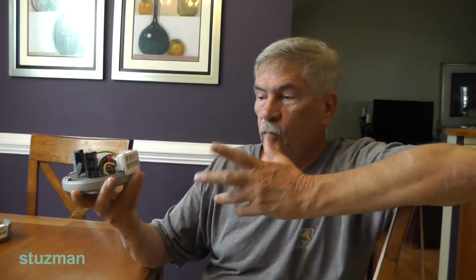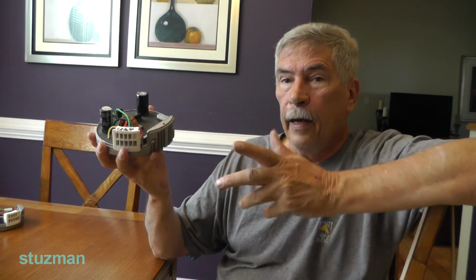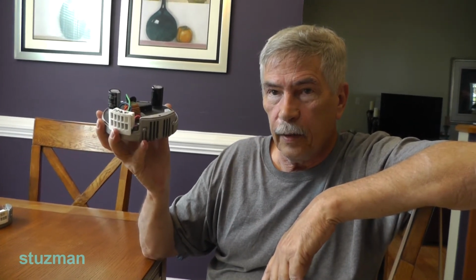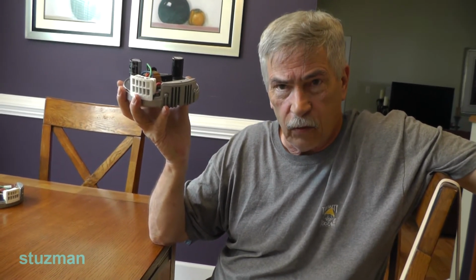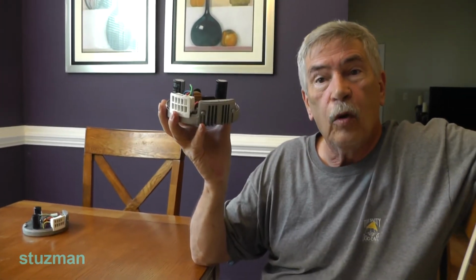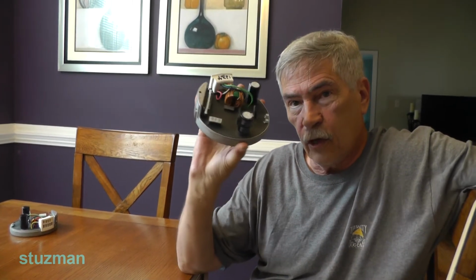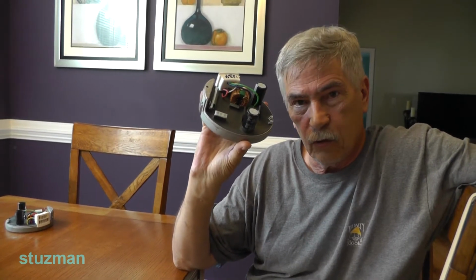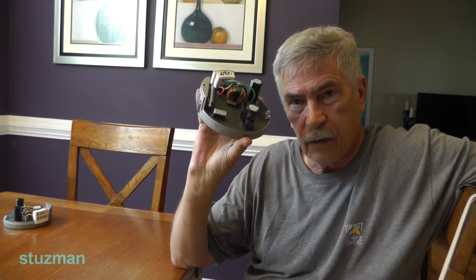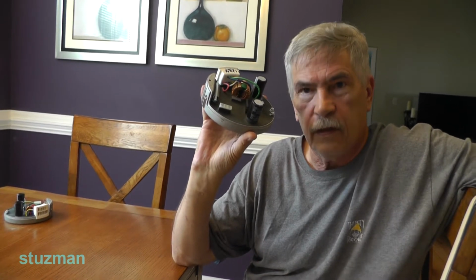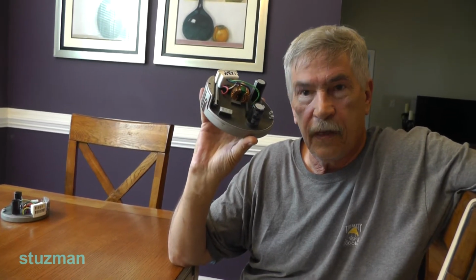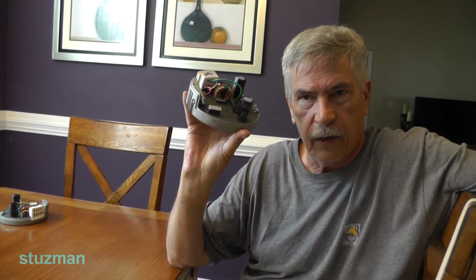So what do we do then? As I said, the motor could run backwards. So what we could do, and I don't know for 100% this will work, but the motor itself is like a three-phase motor, so it's 3 leads. What I'm going to do is swap 2 of the leads if the motor runs backwards, and hopefully this motor will run in the other direction. Because this unit is already pretty much programmed, so if I take 2 of the leads on the motor and swap them, hopefully this thing will run the other direction if it goes in the wrong direction.